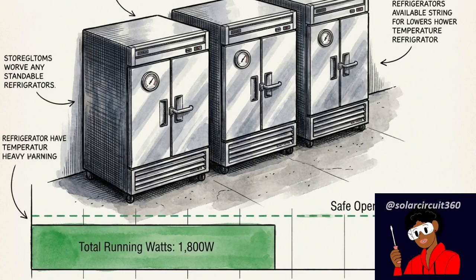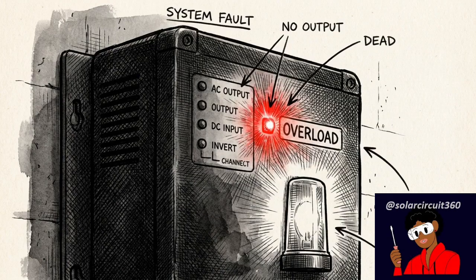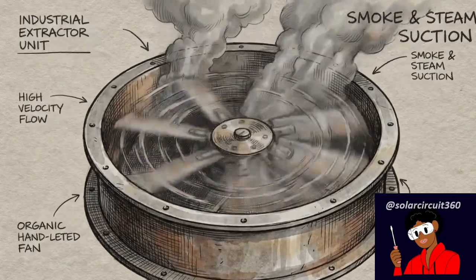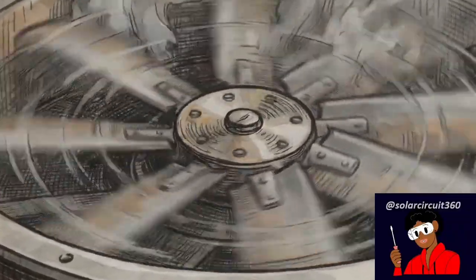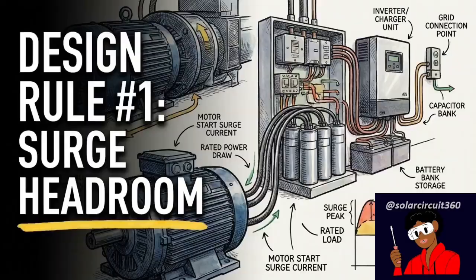The continuous running watts of those 3 fridges are well under the safe limit, but that overlapping transient spike instantly triggers a hardware overload, shutting the entire system down. Factor in massive extractor fans pulling smoke out of the ventilation ducts, presenting their own reactive current demands, subjecting the inverter to continuous, hammering stress. Sizing the alternating current side of a commercial system must always be dictated by the maximum transient surge headroom. Continuous running watts are simply a baseline.